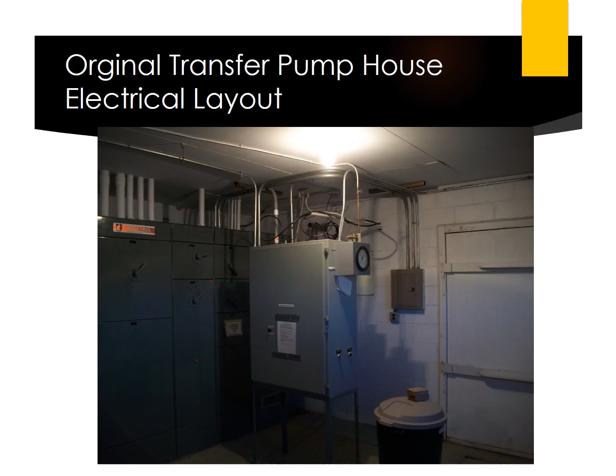2 75 horsepower, 200 horsepower, and 150 horsepower pumps were to be fitted with variable frequency drives. The electronic soft starter for the 400 horsepower pump was reused. Properly accessible and sized switchgear, proper lighting both interior and exterior, and an Ethernet-based control system were to be installed.